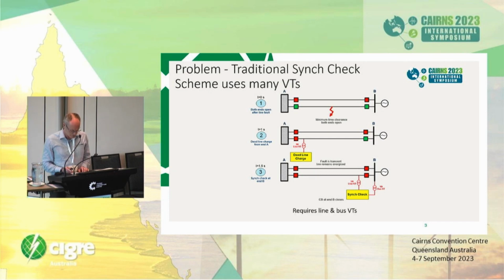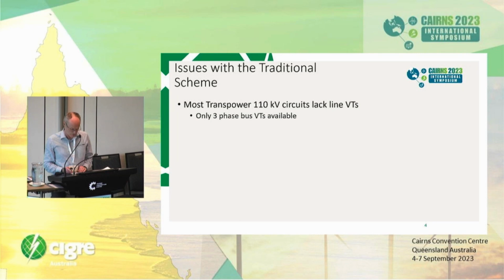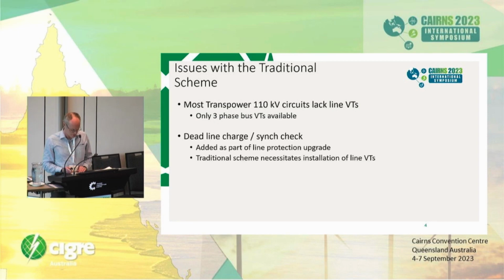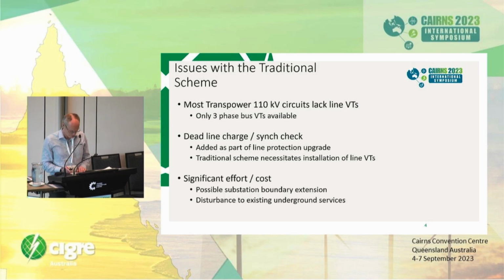For this traditional scheme, a combination of bus and line VTs are required at each end of the circuit. The problem is that most Transpower 110 kV line circuits lack line VTs. Bus VTs are standard. A synchronism check scheme is generally only added where required as part of a line protection upgrade, and this traditionally would involve installing line VTs. However, with more embedded generation, a synchronism check scheme is required more often. With additional protection and VTs, there is significant cost and effort.